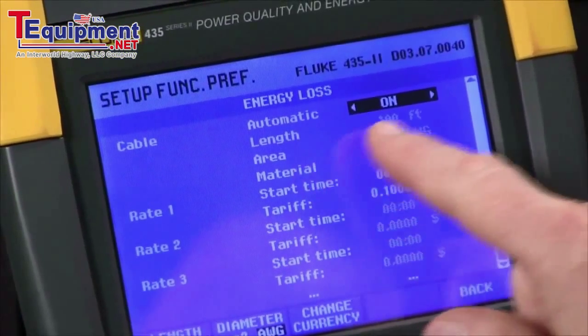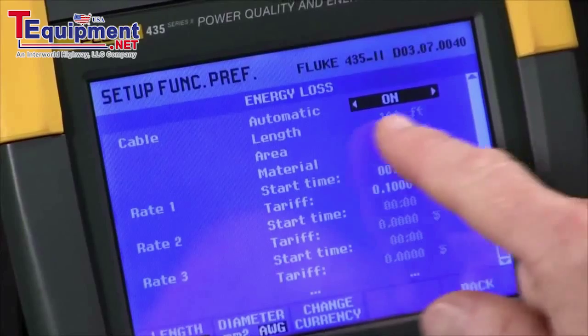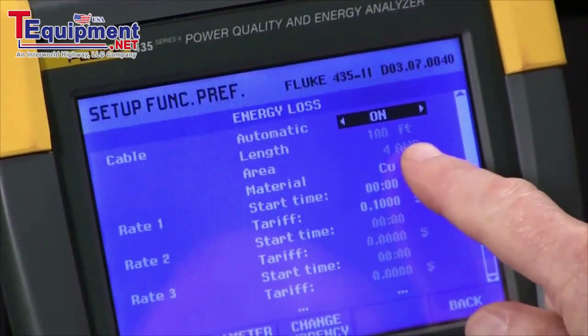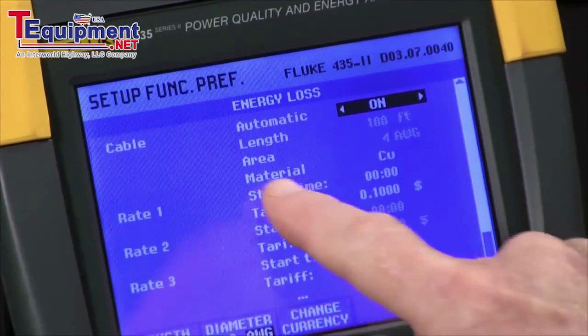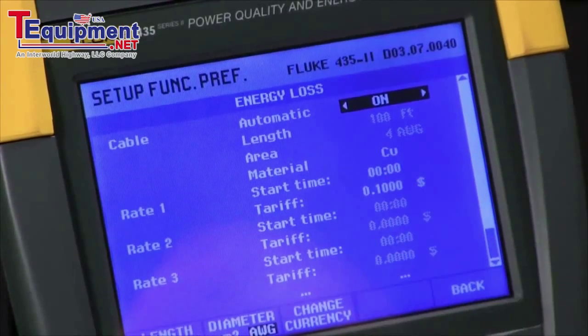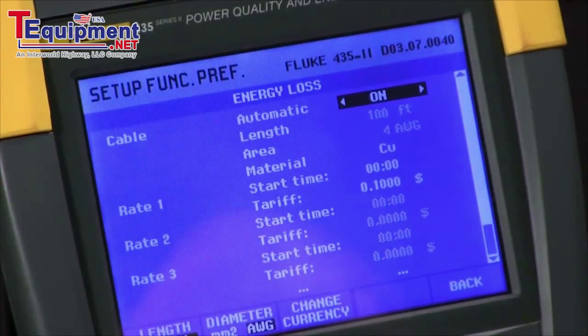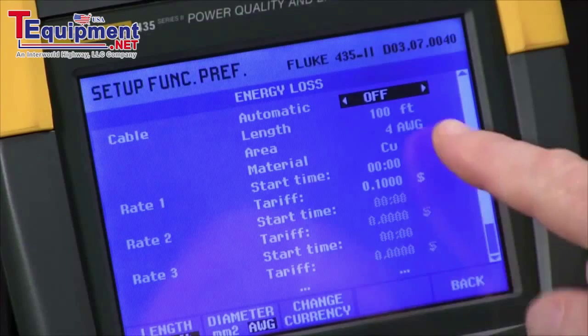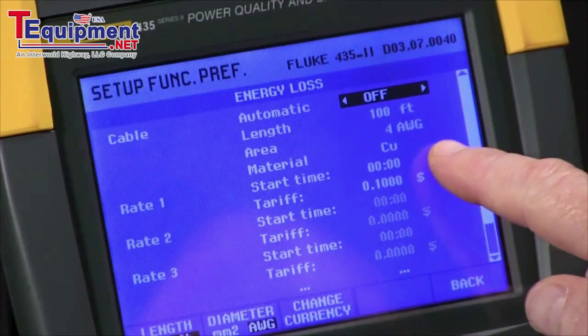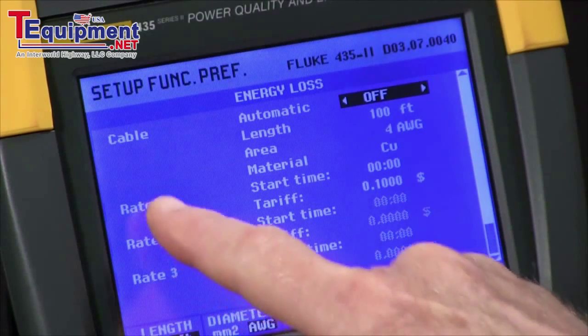At this point you'll see we have a cable section we configure. If we leave the automatic set to on, we assume a three percent loss and can't make any adjustments. If we toggle that off, then you can make adjustments to the length and the gauge of the wire.